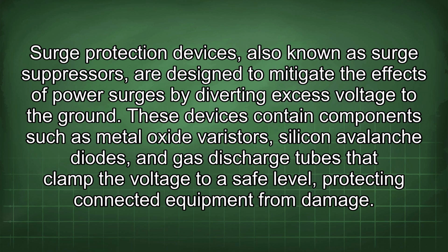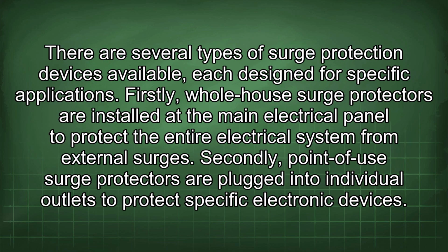Surge protection devices, also known as surge suppressors, are designed to mitigate the effects of power surges by diverting excess voltage to the ground. These devices contain components such as metal oxide varistors, silicon avalanche diodes, and gas discharge tubes that clamp the voltage to a safe level, protecting connected equipment from damage. There are several types of surge protection devices available, each designed for specific applications. Firstly, whole-house surge protectors are installed at the main electrical panel to protect the entire electrical system from external surges.